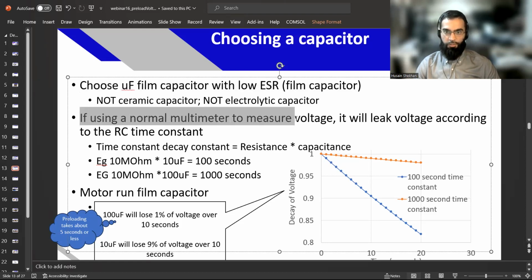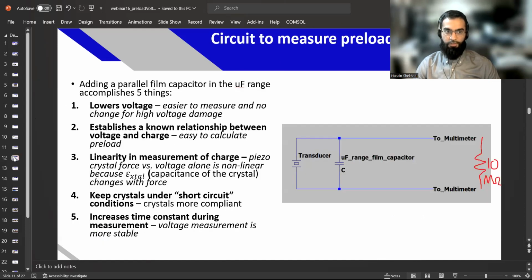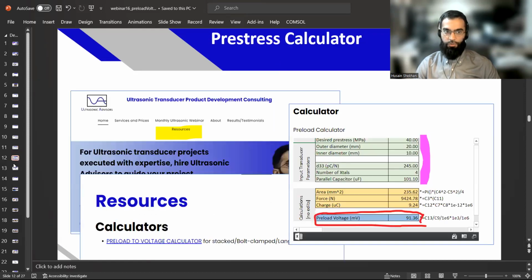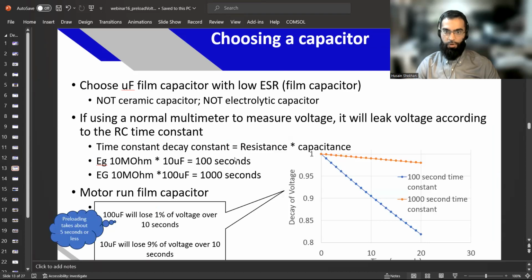If you're using a normal multimeter to measure voltage, it will leak out voltage according to the RC time constant: your microfarad film capacitor in parallel with the resistance of your measurement source, which is going to be 10 mega ohms.